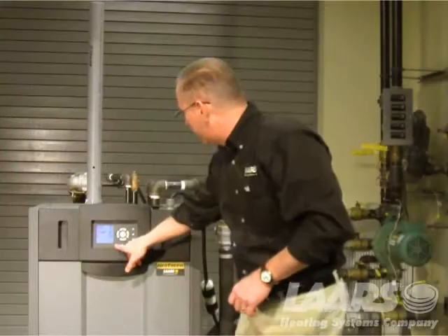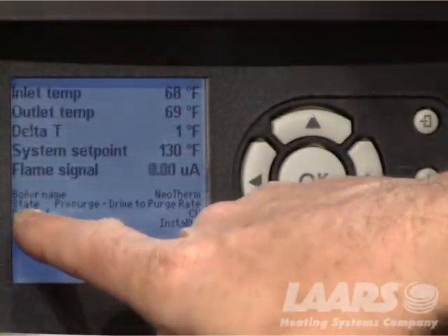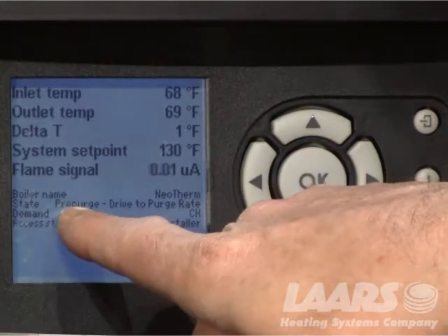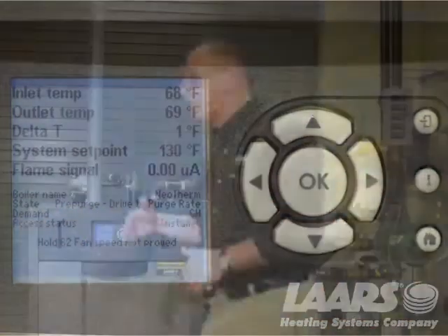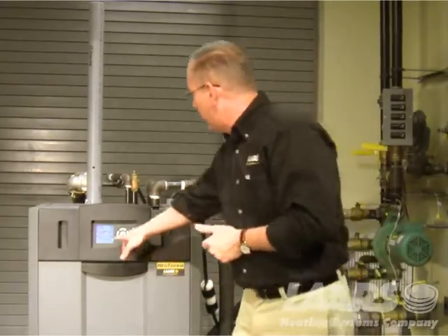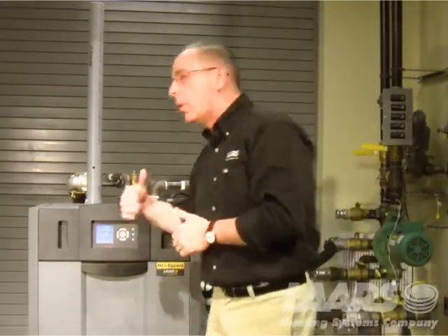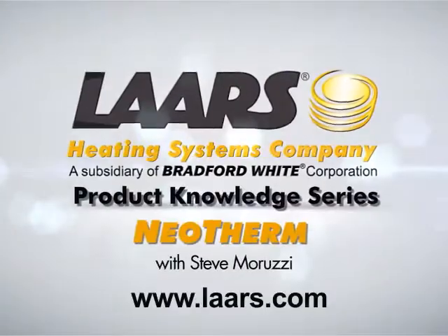Now that we've reset it, we can actually see the state and the information. We're going to pre-purge the drive. What that is, is the blower is actually running to clear the chamber of any flue gases. From there it will go into ignition and then eventually you'll see running. We'll see you later.